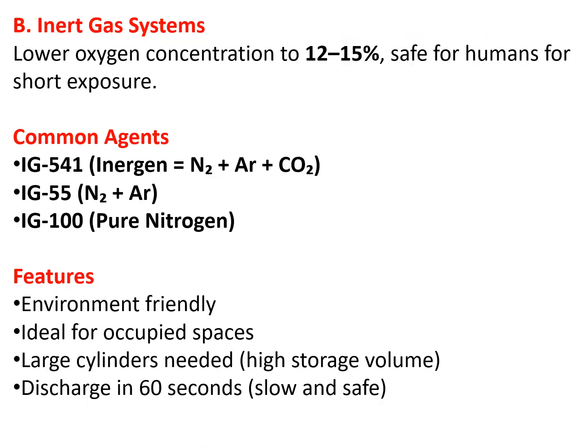Dear friends, the second total flooding system is known as applying inert gas systems. The inert gas system lowers oxygen concentration to 12-15%, safe for humans for short exposure.